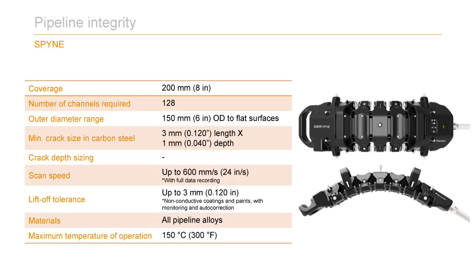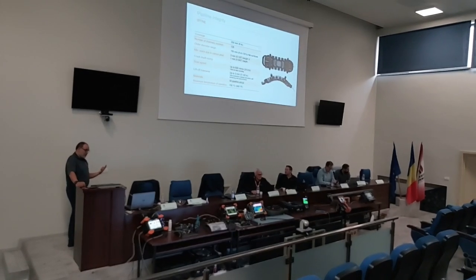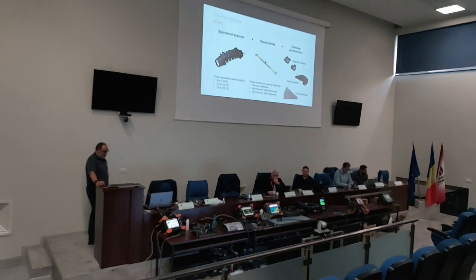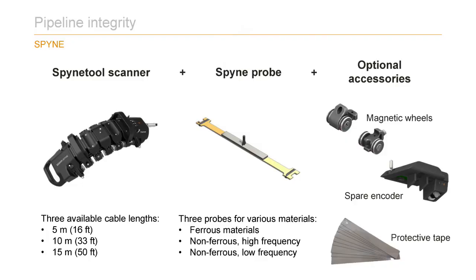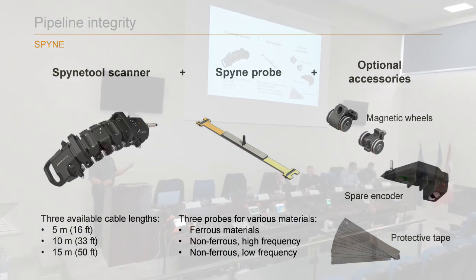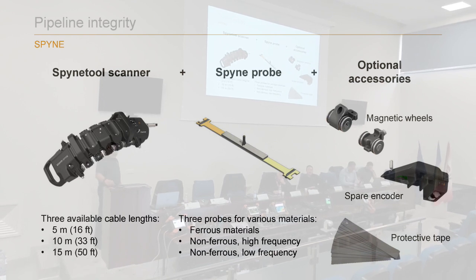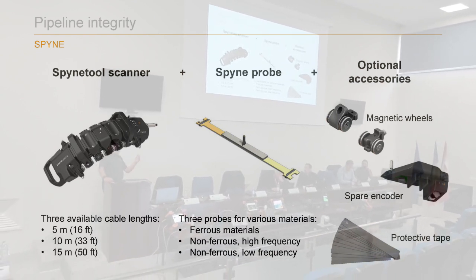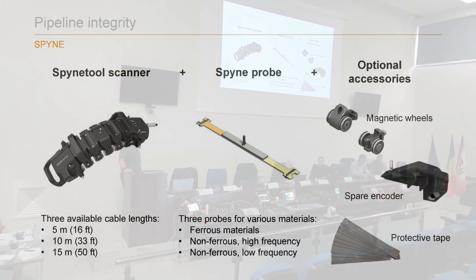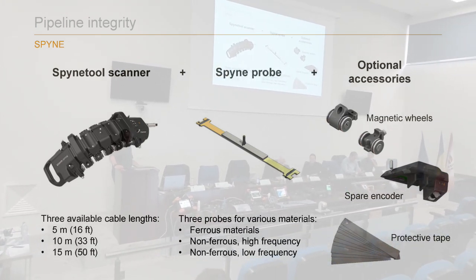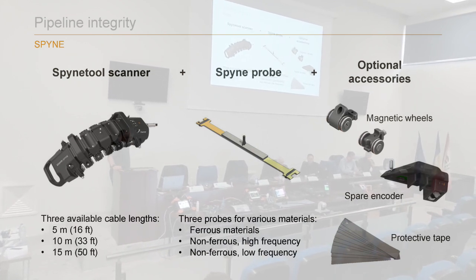I'll skip that slide, just an overview of the range and specification of the probe - scan speed, liftoff tolerance, etc. The temperature of operation too - we can use the probe up to 150 degrees C, which is important information. Basically, the Spyne is made of a scanner with different lengths of cable, with a probe that can be replaced, different models, different frequencies, meant for ferritic or non-ferritic materials. Then you have magnetic wheels if necessary on carbon steel. Of course, if you're inspecting stainless steel pipe, the magnetic wheels become useless. Spare encoders, protective tape - because you want your probe to last as long as possible.